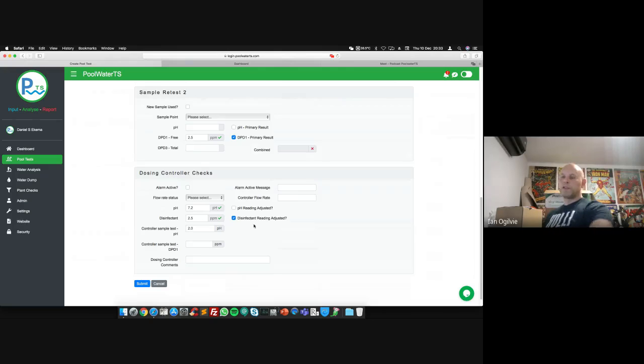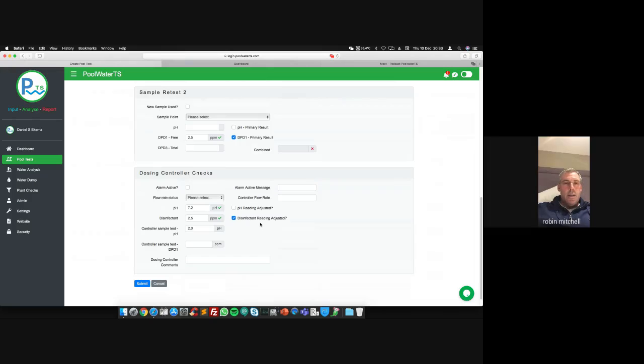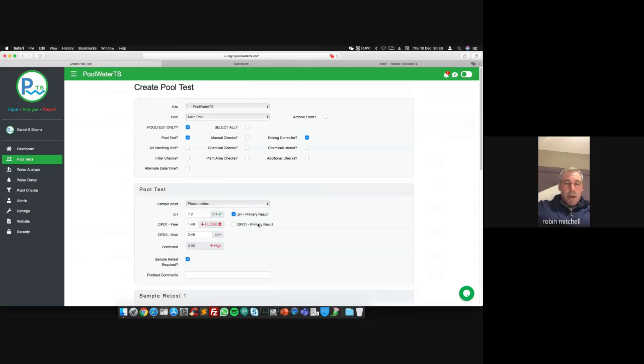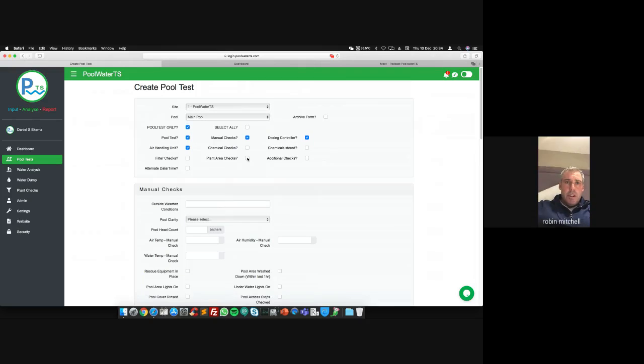Like you said, Dan, obviously you've got a problem with a probe just now. Yes. So if you saw that, oh my God, every 2 hours they're recalibrating this probe, there's got to be something wrong with the probe or something wrong with the system, whereas just now it's usually a clipboard which they may or may not sign off. In the plant room. It's massive, Robin, isn't it? Oh, I've just been delivering a pool plant operators course today, and that's a major part of the subject, on water testing, is how you actually deal with the controller after you assess your water test. Yeah, definitely.